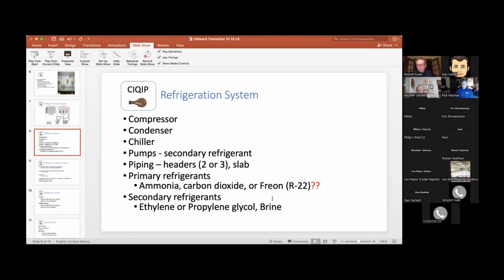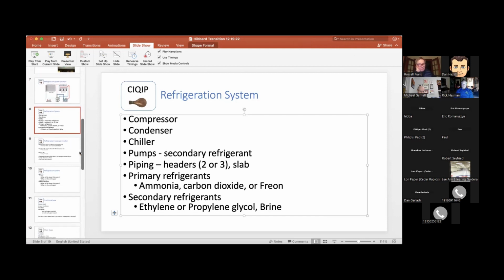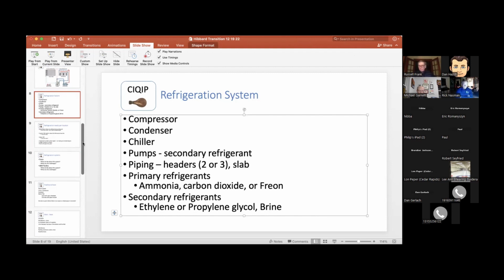Can you just talk about what each one of these components does, not too long, just a short description? Okay, the compressor compresses a low pressure hot gas, warm gas, into a high pressure hot gas. And when it goes in, it's a hot gas, it then transfers to the condenser. The condenser will blow air through it, or water, whichever, to lower the temperature of the gas in the vessel. When it gets below the dew point of the gas, it condenses back into a liquid, and it's then shunted to the receiver. When it's in the receiver, before it goes into the chiller barrel, it will go through an expansion valve. That's just a very small orifice. It'll be like 175 pounds on one side of the orifice, and it'll be 30 pounds on the other. As that gas expands through that orifice, it absorbs heat, and it creates the refrigeration effect.